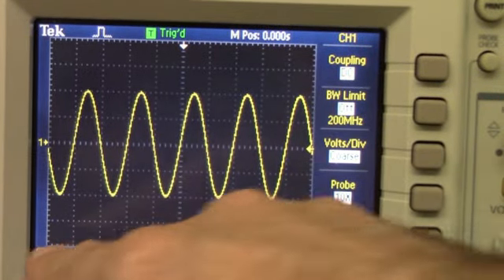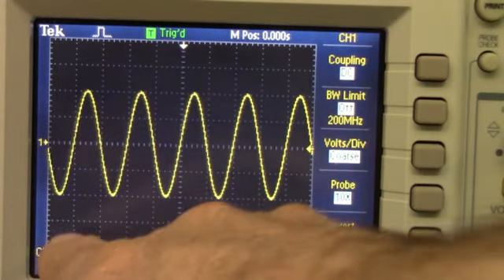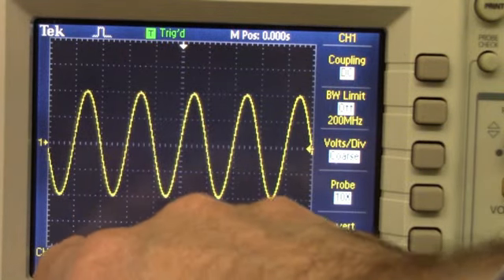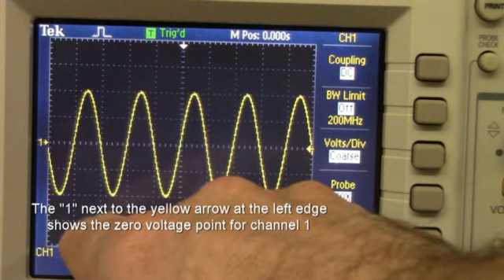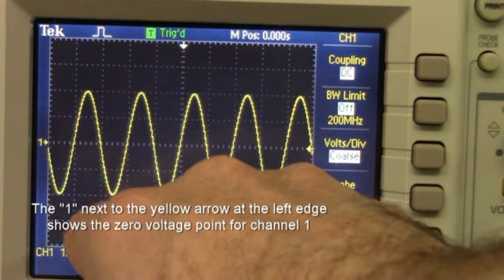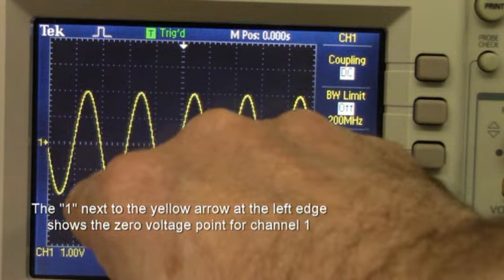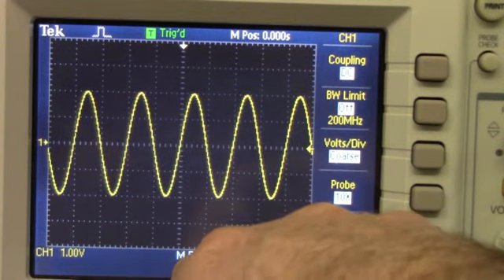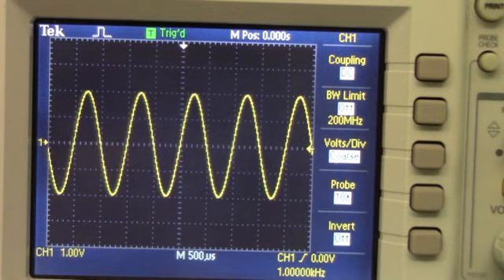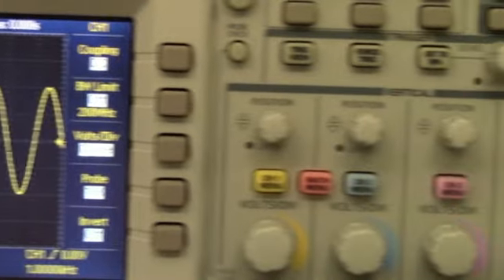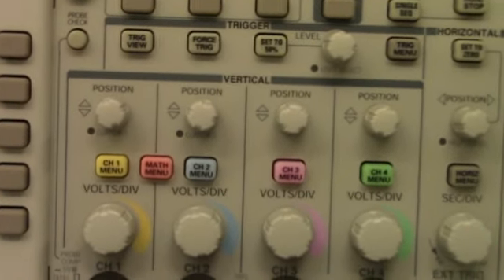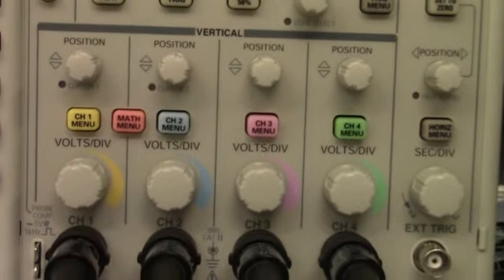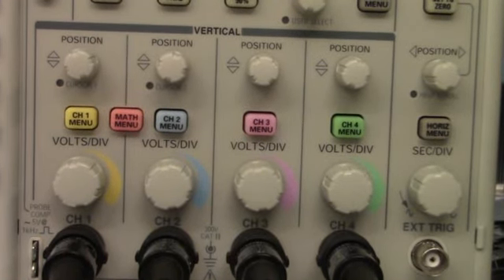shows us a picture of time running horizontally and voltage running vertically. In this case, each division, and that's a 1 centimeter division, there's 8 vertical centimeters, is 1 volt. Those are broken up into 5 separate sections, so we've got 0.2 volt, 0.4, 0.6, 0.8 to get 1 volt per division. Horizontally, each division is 500 microseconds. We have a set of controls that allow us to control both the vertical sensitivity, that's the voltage sensitivity, and the horizontal, the time sensitivity, sometimes called the time scale.